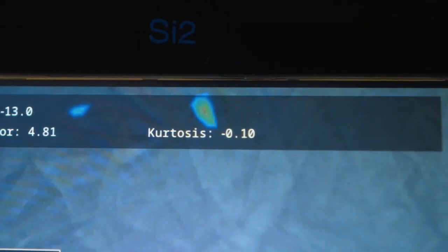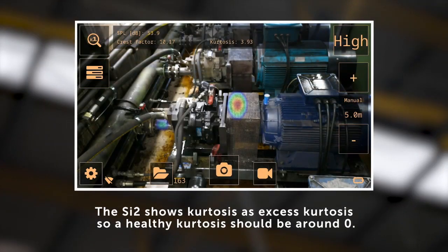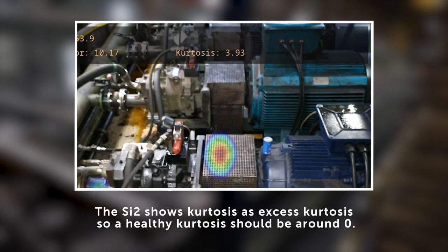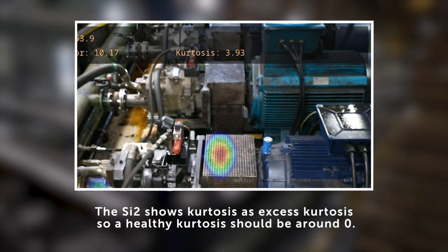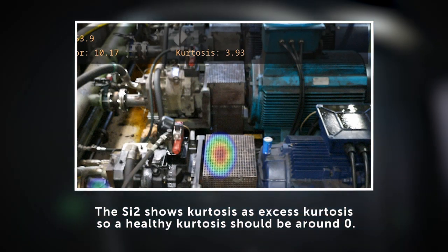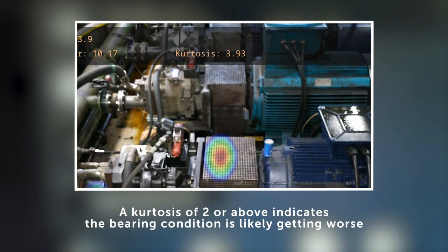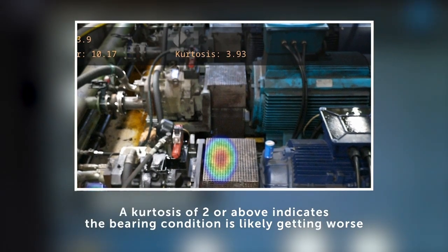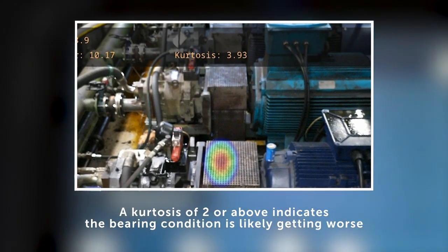Kurtosis is a measure of the distribution of the samples in the sound signal. The SI2 shows Kurtosis as excess Kurtosis, meaning that a healthy bearing will show a Kurtosis around 0. A Kurtosis of approximately 2 or above is likely to indicate that the bearing condition is getting worse.